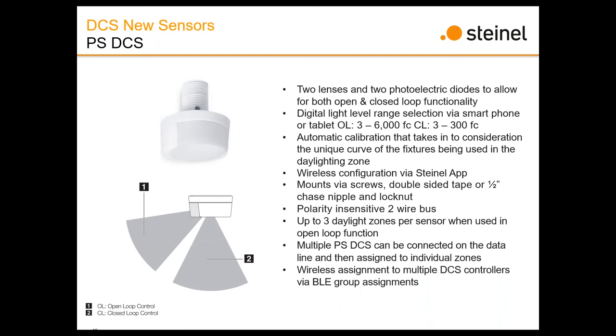So it makes it a very easy way to commission and set your daylighting set points. Another feature is plug and play: if the system recognizes a photo cell is connected, it assigns it to zone 1 and automatically sets it to roughly 30 to 50-foot candles at desktop. If you want it very accurate, you have to go through that commissioning process I just explained.